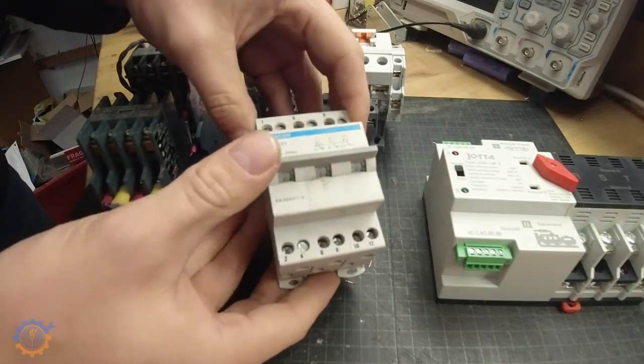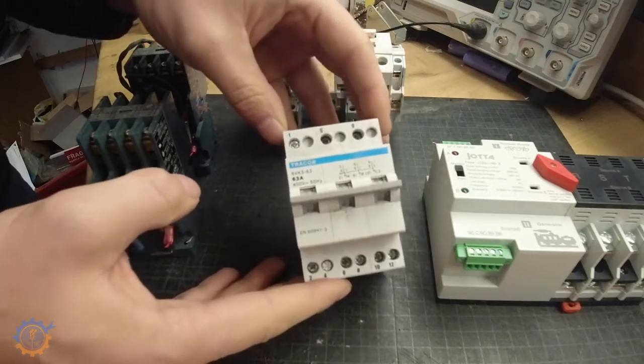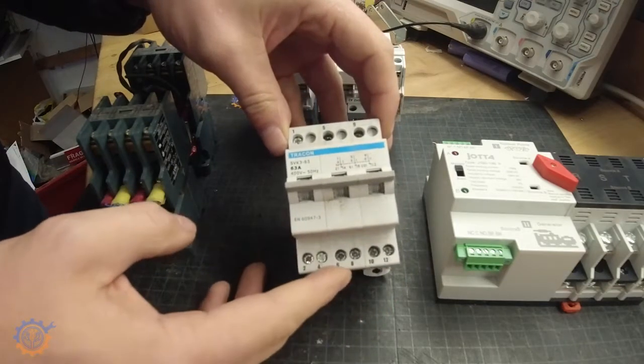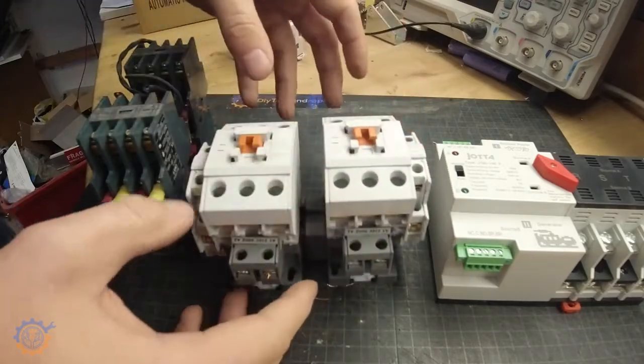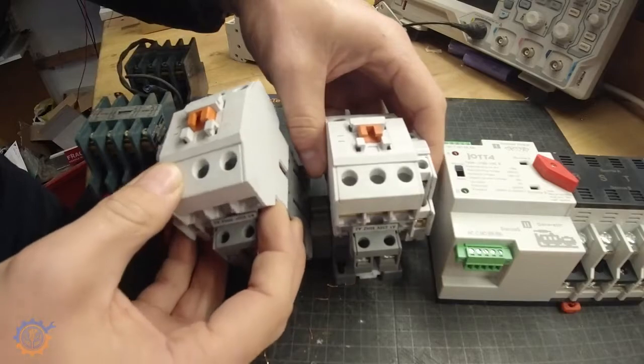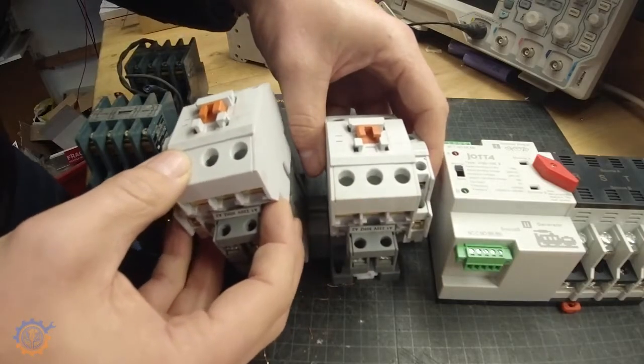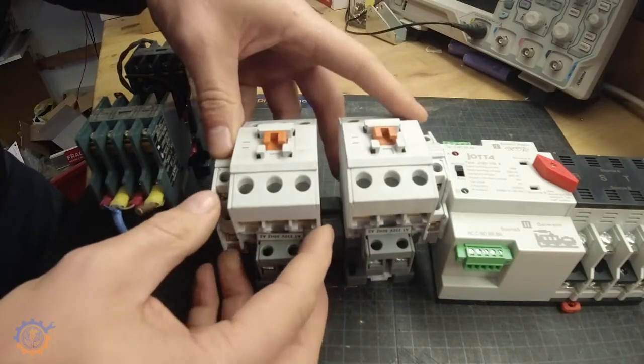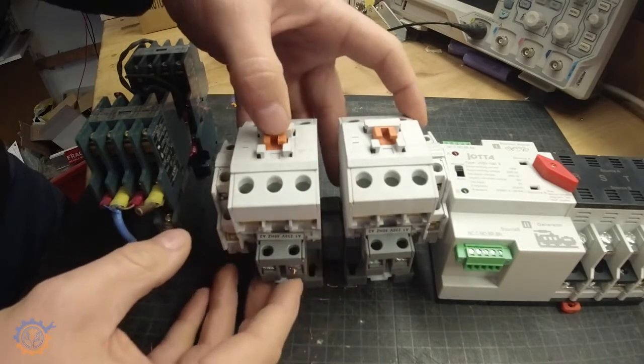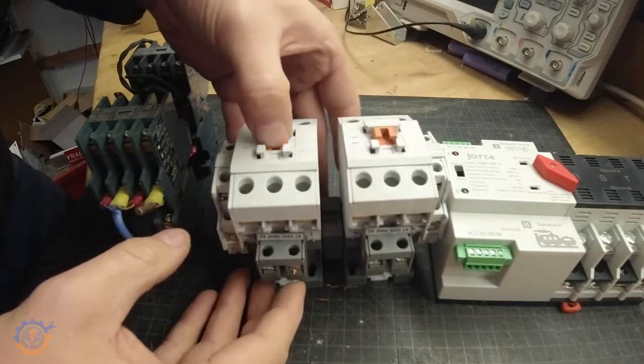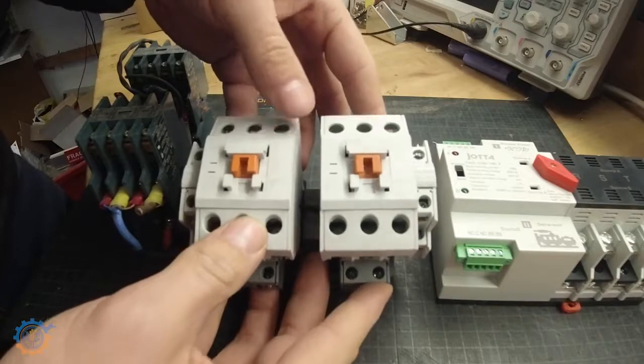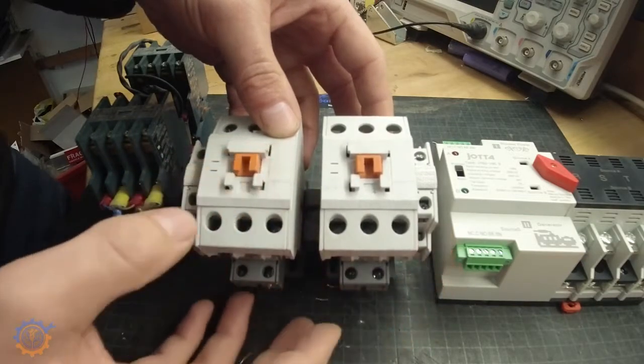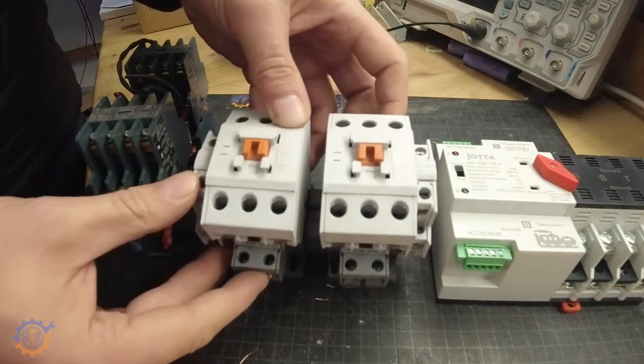With that said this one is totally manual but that's actually what I'm using here in my house now except mine is four pole instead of three. Automatic transfer switch on the other hand, here you have a three pole automatic transfer switch where you hook them together. And in between them you will have a mechanical interlocking. Those are contactors that you either draw this one or draw this one and power goes through. As long as you have this side port here you can hook them up as an automatic transfer switch.